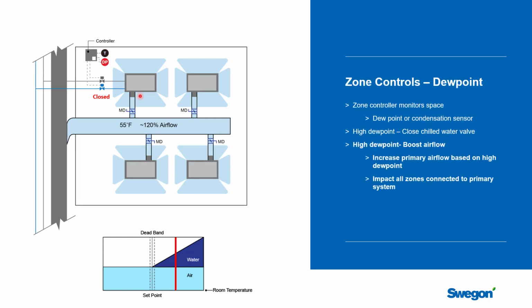So one of the other things you could look at doing would be a boost mode, and that would require some thought about how the air handling system was sized. But if you went back and had a little bit of extra capacity in your primary air handling system so that it could get to 110 or 120% of normal design airflow, you could use your dew point sensor to recognize when you might want to go into boost airflow mode.